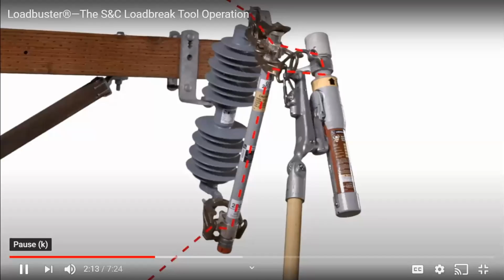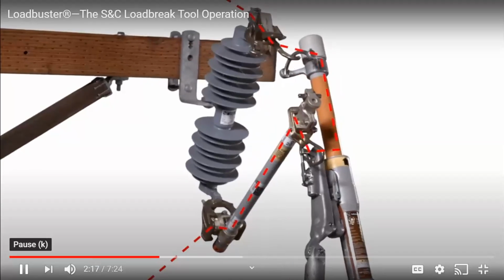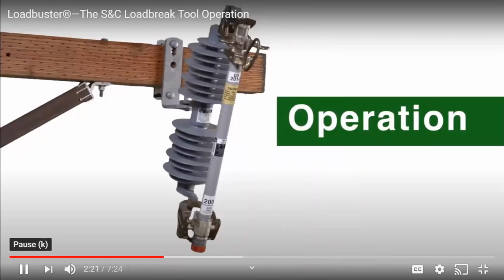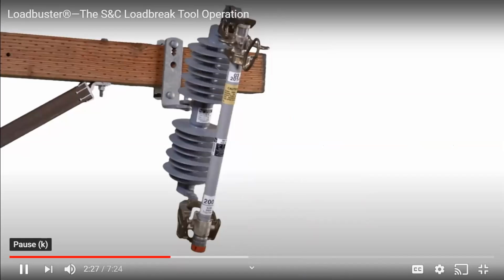Ring of a hook-equipped distribution device. When operated, the load current is diverted through the load buster tool and interrupted within. We will demonstrate operation on an SMD-20 power fuse, but the procedure is equally applicable to fuse cutouts. What size fuse is it? 200 amp. It's a 200 amp fuse, yeah.